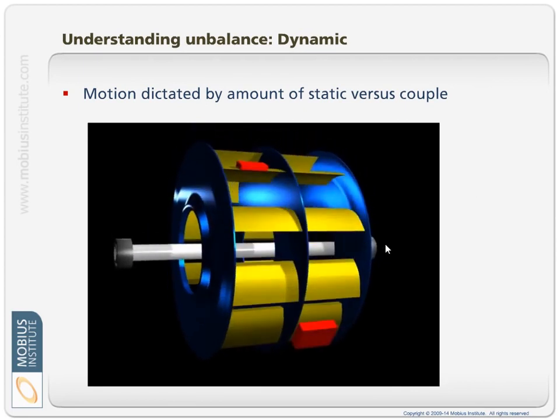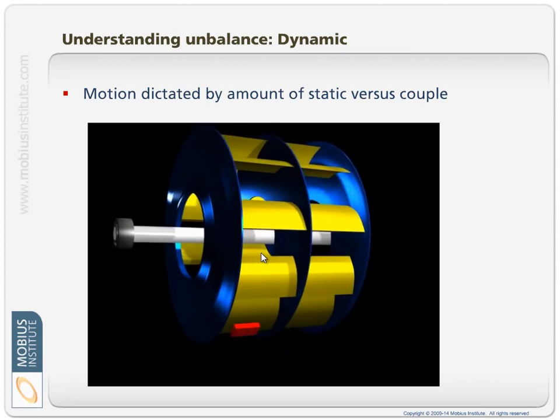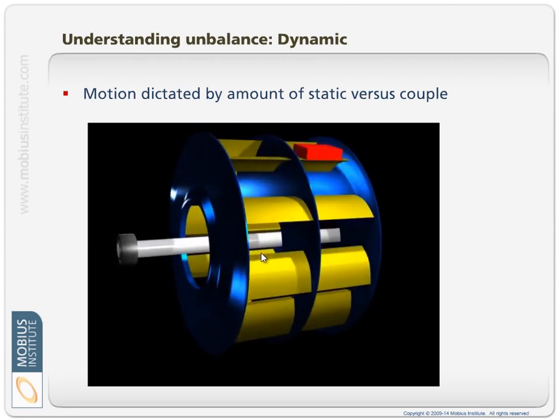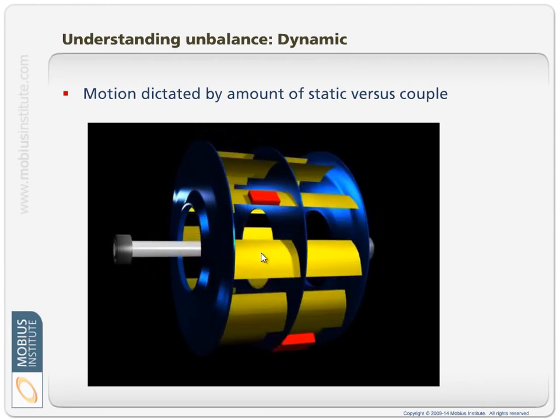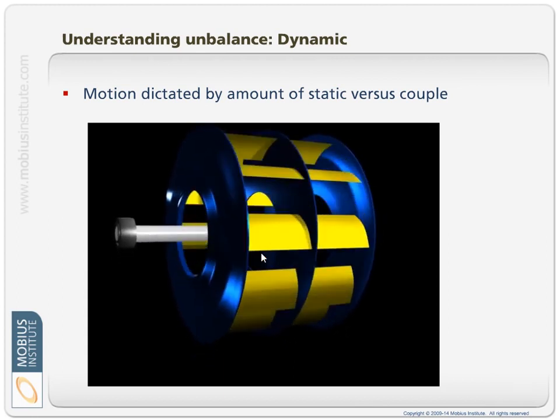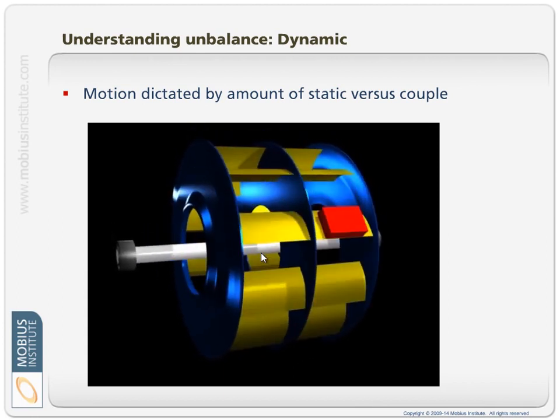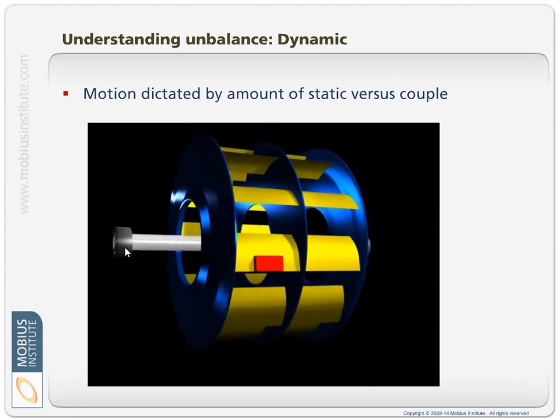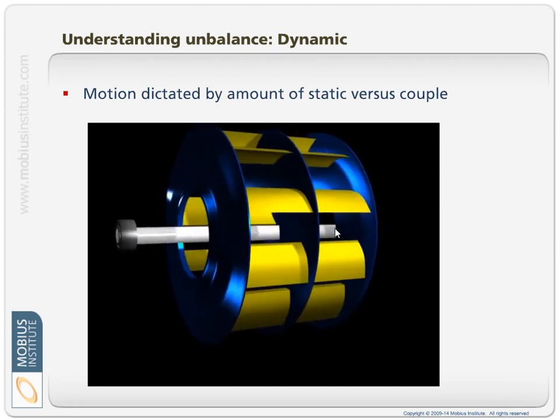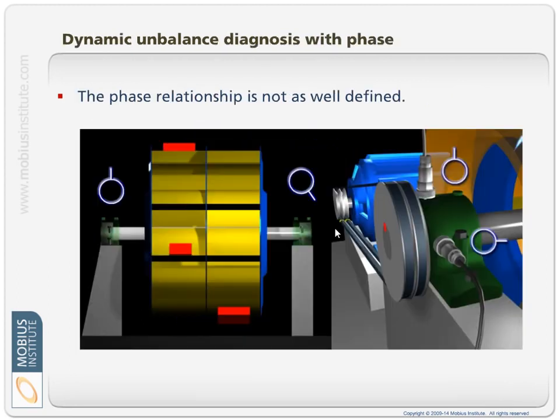The rotor's longer, the distribution of dirt buildup along the fan is not uniform, so therefore, if you like, it's more out of balance in one plane than another. Either way, that is still circular motion, but from one end to the other, it's not in phase like it was just before.